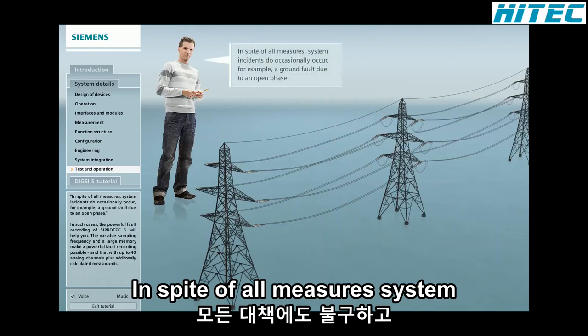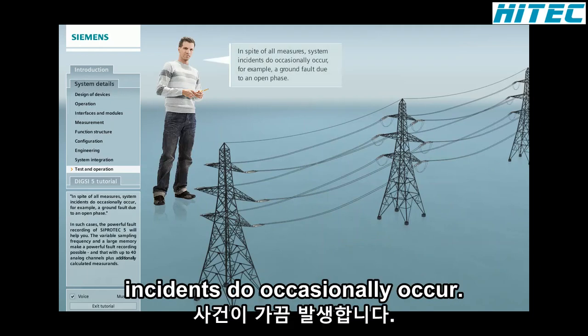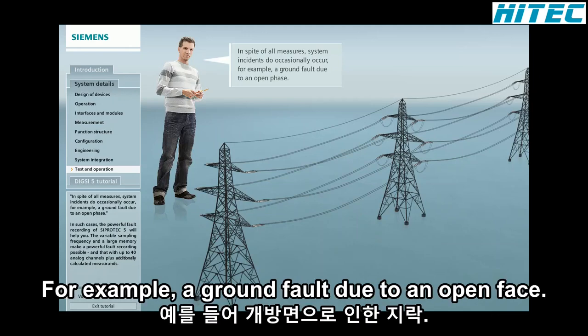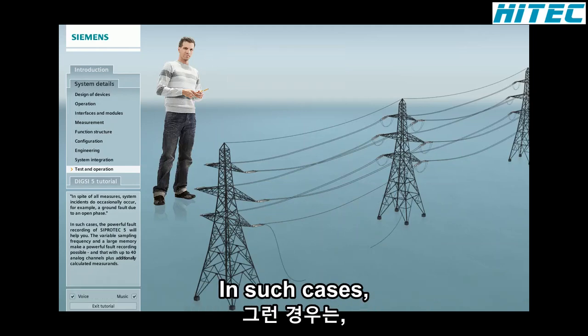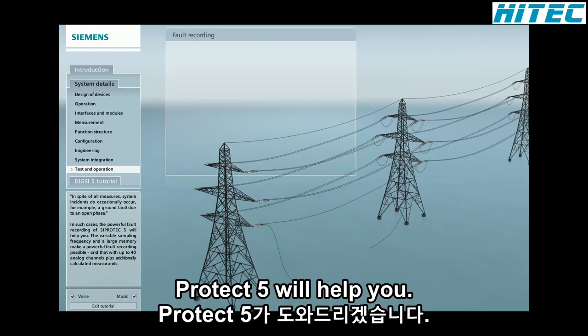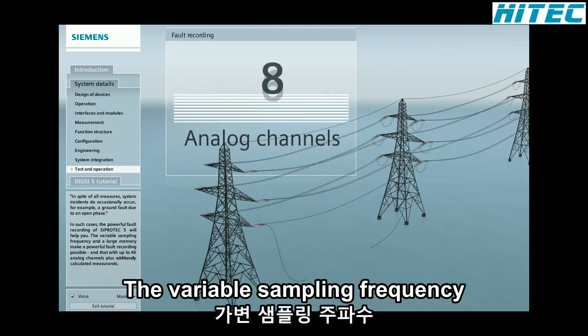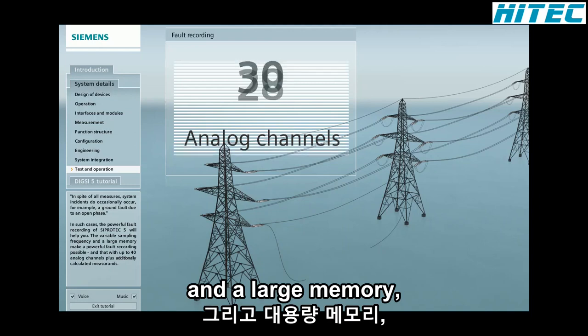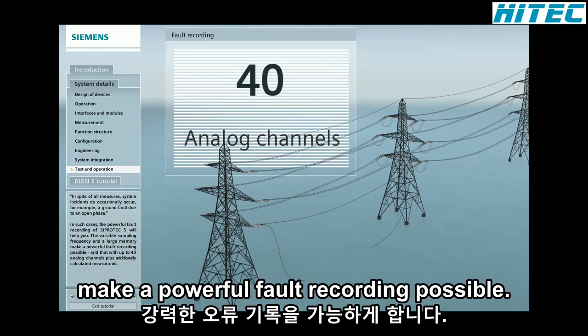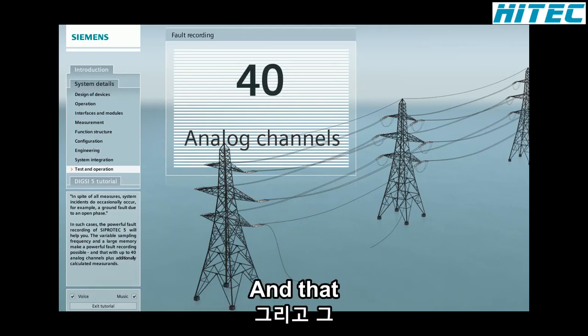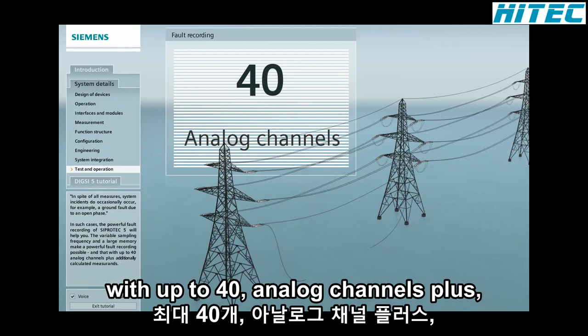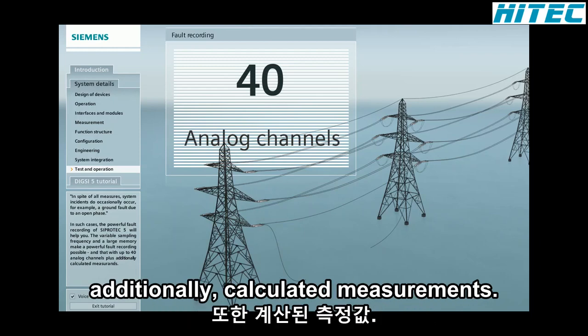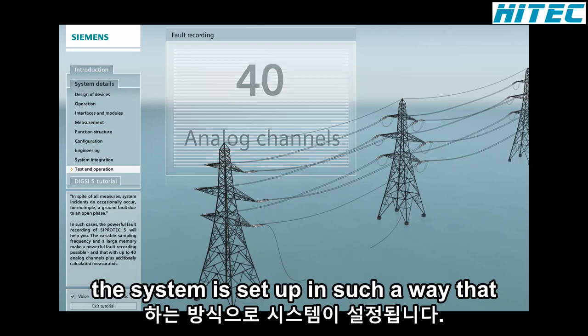In spite of all measures, system incidents do occasionally occur. For example, a ground fault due to an open phase. In such cases, the powerful fault recording of SIPROTEC 5 will help you. The variable sampling frequency and a large memory make a powerful fault recording possible, and that with up to 40 analog channels plus additionally calculated measurements.